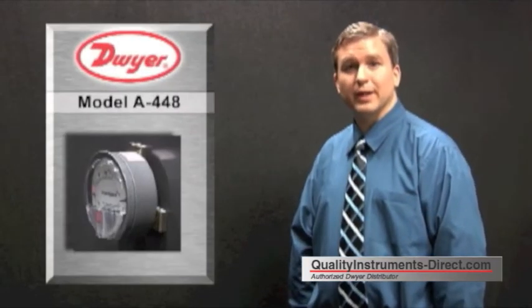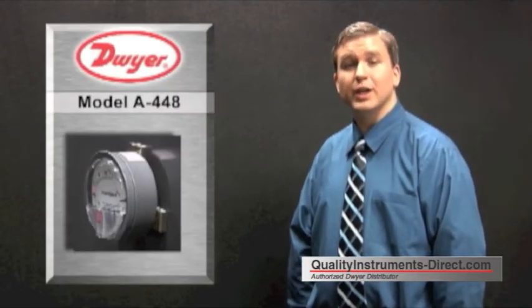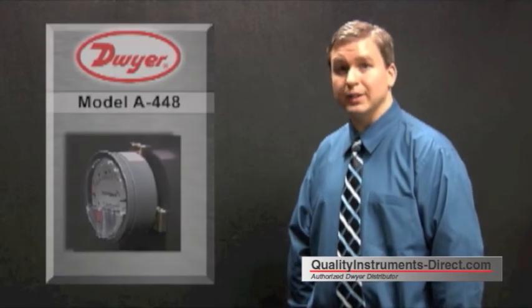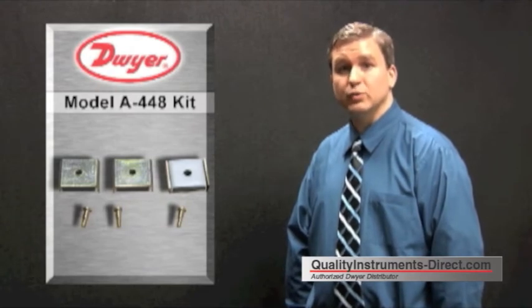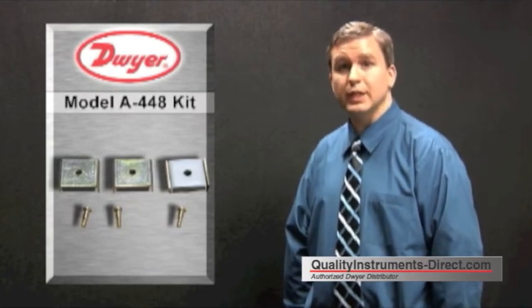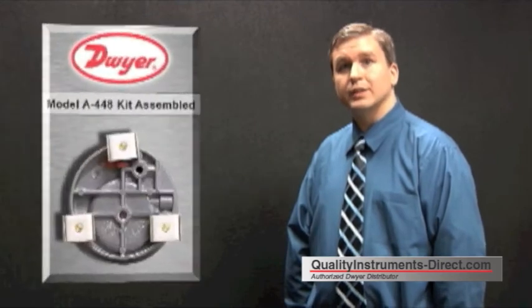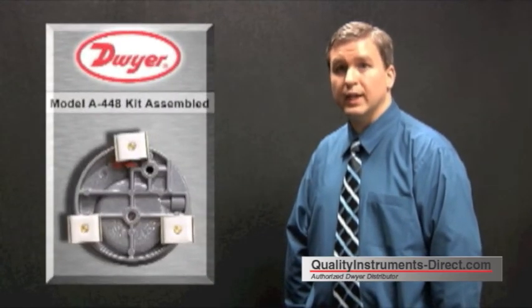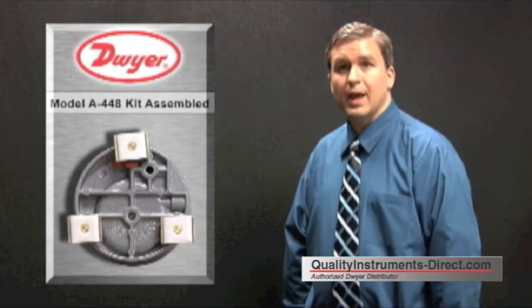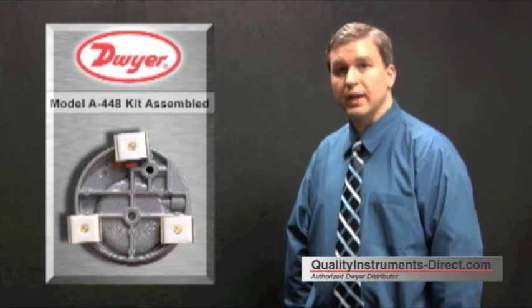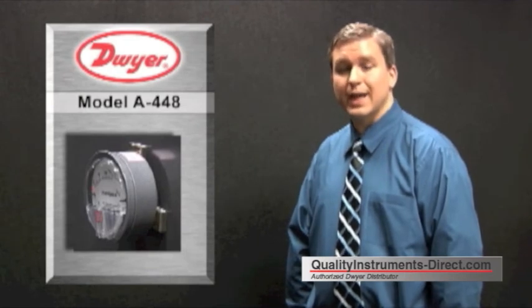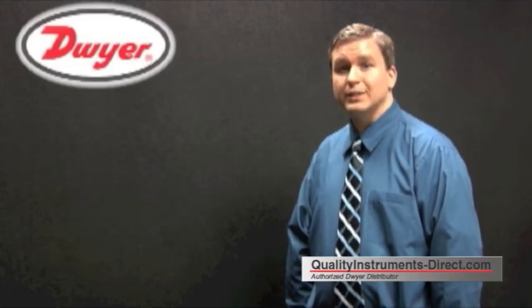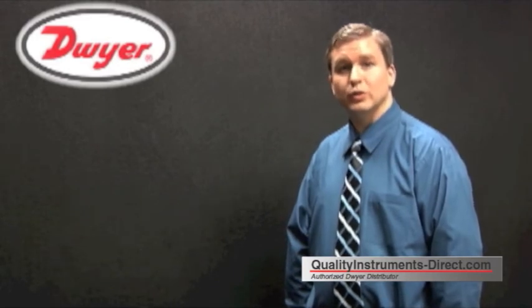Another means to mount the Magnehelic Differential Pressure Gauge is with our A-448 magnetic mounting kit. These magnets allow the gauge to be mounted to any metal surface with magnetic properties such as a standard air duct. Simply take the threaded screws provided with the A-448 kit and insert it through the back of the magnets into the back of the gauge. Once complete, it easily adheres to any metal surface. That makes it ideal for portable applications where it is required to move the gauge frequently during tests.